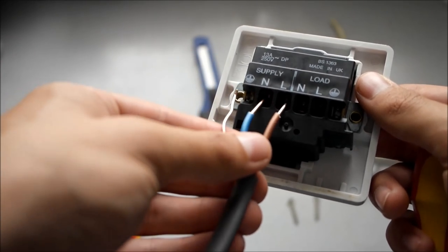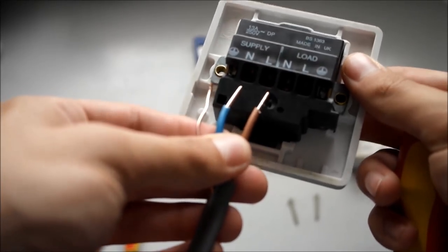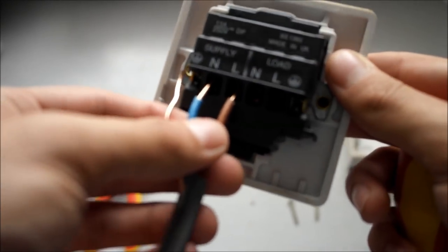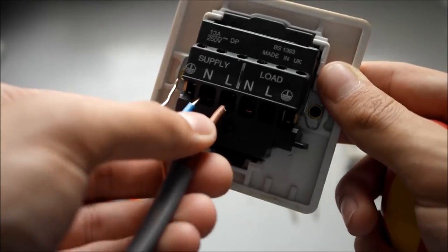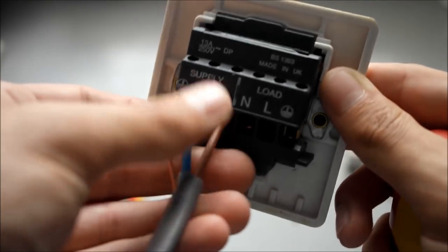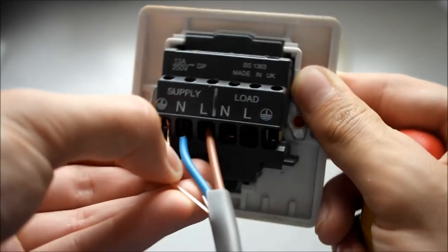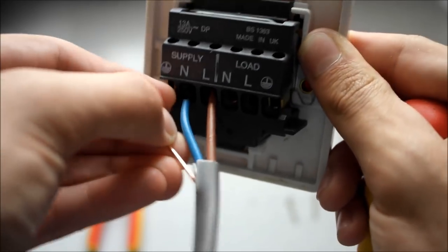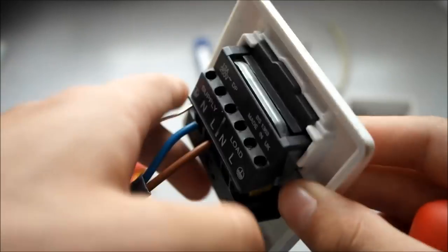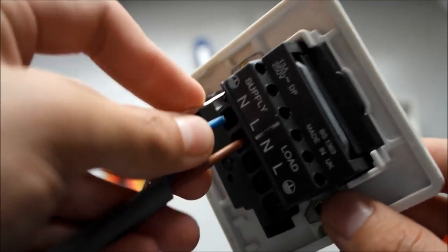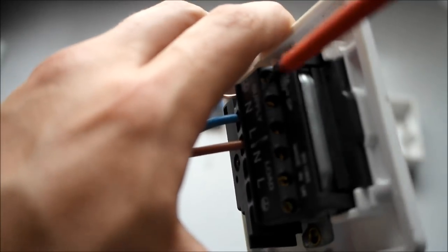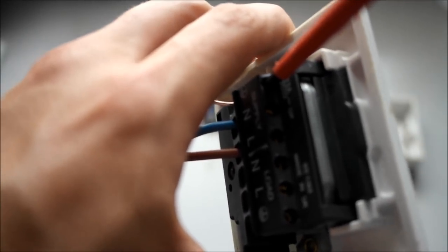This cable as you know is twin and earth and like I say it should be insulated on the earth cable. When you make this termination make sure there is no copper outside the terminal or otherwise it could potentially be a fire hazard. Then just tighten up the screws in the terminals.